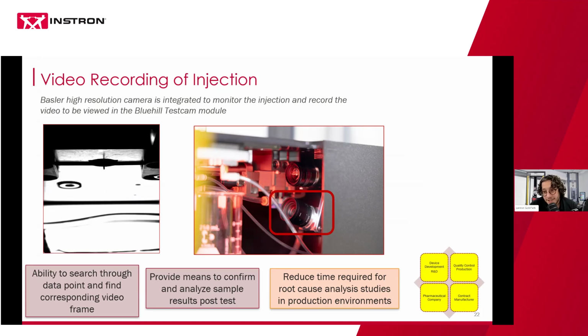The number of times I've seen that just having the capability to go back and see, for example, that the needle came out at a pretty intense angle, maybe 60 degrees off. That could have impacted the fluid going into the beaker. It could have impacted the depth of the needle that was measured. If you did not have that video recording, you'd have very little means to go back and identify what happened. Maybe you can scan the device to try and assess it or disassemble it, but it's a lot quicker if you just have this video file available. So this is really important.